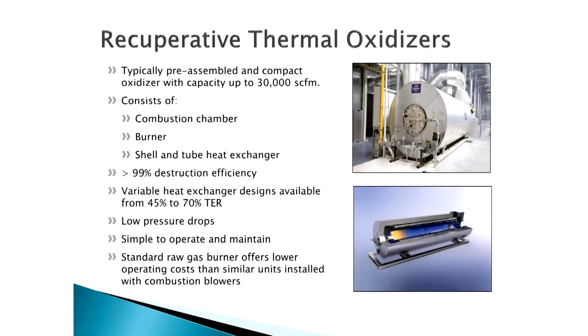Recuperative thermal oxidizers are somewhat similar to an afterburner in that you have an integrated heat exchanger that works with the actual afterburner. Basically, these are deployed on slightly lower concentration gas streams that do not have any liquids in this case. They're typically a combustion chamber, a burner, and they're integrated with a primary shell and tube heat exchanger.